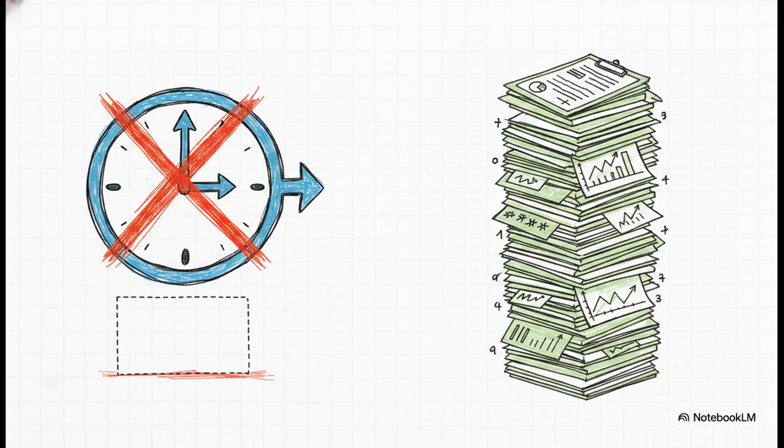This whole route is based on one hard truth. You cannot go back in time and hold a design review that never happened. Now, you are permitted to use field experience, stuff like years of use, install base, complaint history, as evidence in your rationale. But hear me on this, field experience cannot magically replace the architecture you never bothered to write down, and it absolutely cannot substitute for a real, forward-looking risk analysis.